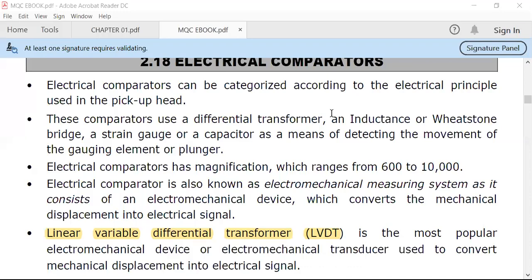These comparators use a differential transformer, an inductance or a Wheatstone bridge, a strain gauge, or a capacitor as a means of detecting the movement of the gauging element or plunger. So differential transformer is one device, Wheatstone bridge is one device, and strain gauge and capacitor is one device. These different types of electrical devices are used to detect the movement of the plunger.